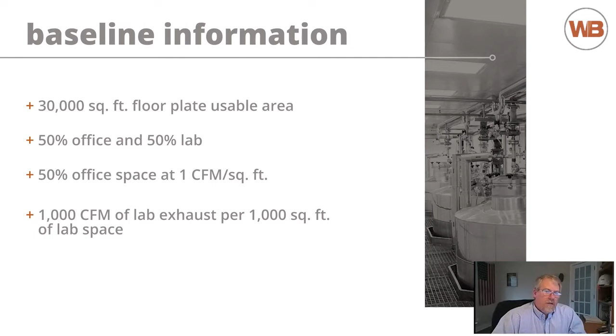And think about the office space, and these are just general loads for space, sensible heat gain or space loads in an office space. So we just blanked it out at 1 CFM a square foot. We also assumed in this particular example 1,000 CFM of lab exhaust per 1,000 square feet. So that just gives you a pretty straightforward ratio of comparison. And it's important, when we talk about master planning buildings, that there are more buildings available with tighter floor to floors.